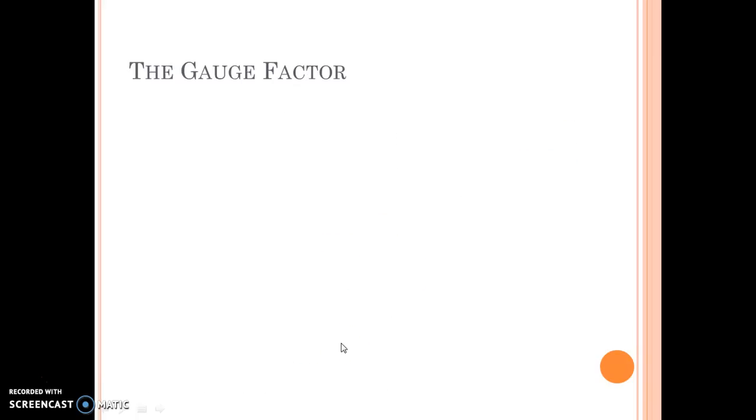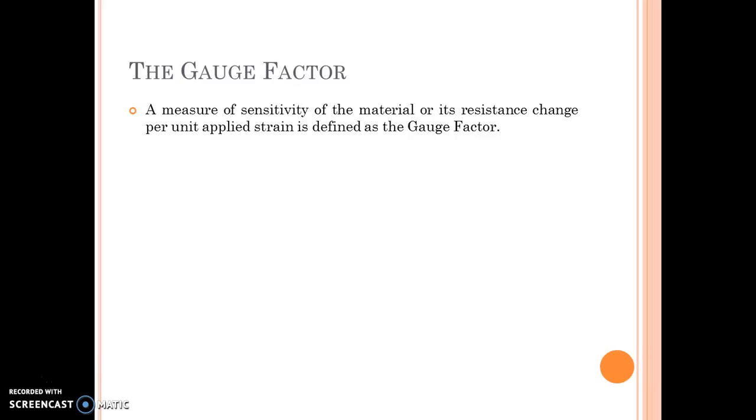Now this is something very important, the gauge factor. The measure of sensitivity of the material or its resistance change per unit applied strain is defined as the gauge factor. So in terms of a formula, it is given as gauge factor is equal to change in resistance per original resistance. So before applying any strain, if the resistance of conductor was capital R, let us assume that now there is a small change in resistance called as dR. So this is the change in resistance per unit original resistance and this is the applied strain.